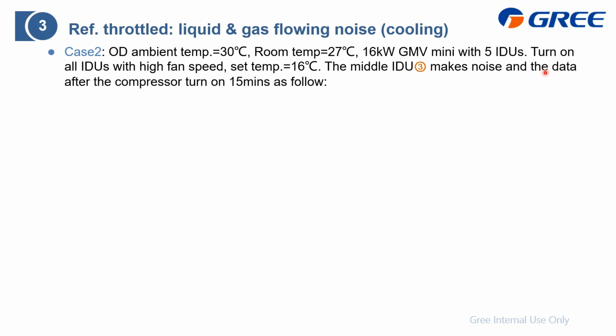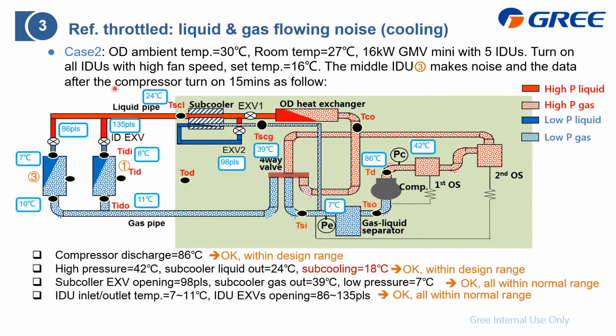We turn on the system and operate for at least 15 minutes. Then we put the data inside the cycle diagram for analysis. So first is the compressor discharge. Okay, within our desired range. And then to check the subcooling: high pressure 42, subcooling liquid out 24. So we get a subcooling degree of 18. Also okay, within our desired range.